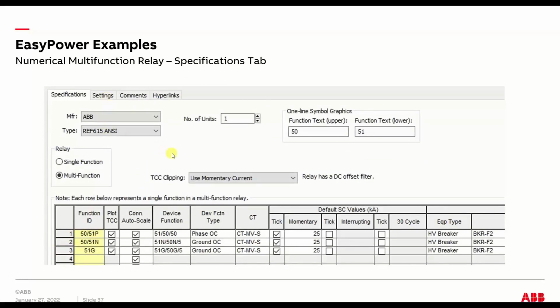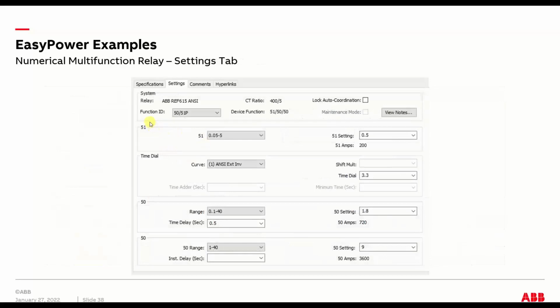And then under the settings tab, this is for device number one, your 50/51P. That's what I called it, so you can call it whatever you want. Then you have your 51 protection. This is the range, which for this case is preset. And then you have your setting, and that's the tap value. And here's your time dial.